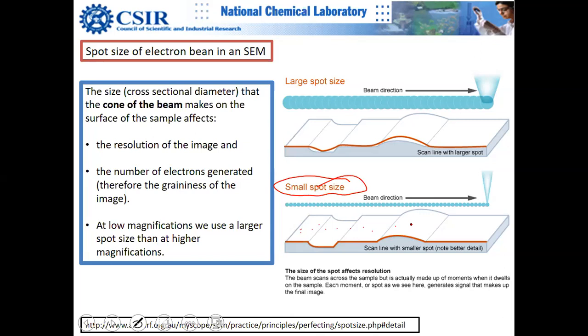Resolution is not just a function of spot size alone — the interaction volume matters too. When the beam enters the sample and generates secondary electrons, it broadens, so outgoing secondary electrons come from a slightly larger area than the beam spot.